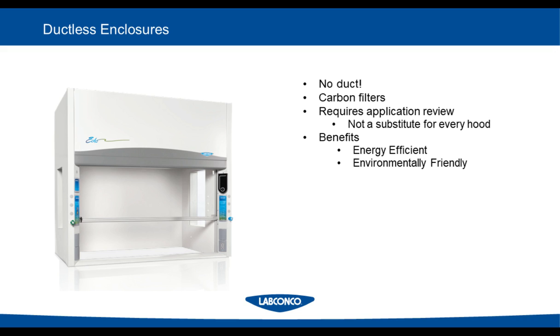The next benefit is that they are environmentally friendly. Ducted hoods will take these chemicals and hazardous vapors and fumes, and they'll exhaust them into the atmosphere. With the ductless enclosure, you're capturing those, and then you're taking these filters that have been loaded with these hazardous materials and disposing of them in an environmentally friendly way. The next benefit is that they are very flexible. They offer flexible installation. They are able to be put in the bottom room of a very tall building where ductwork does not seem plausible. They're able to be put in a building that is very old, where adding new infrastructure would seem very expensive and very labor intensive. So this added dimension of flexibility is a very big benefit of these ductless fume hoods.